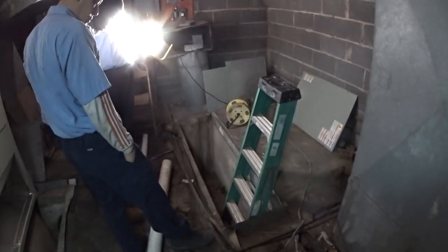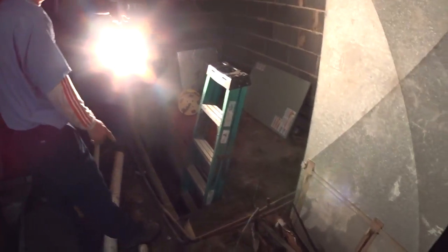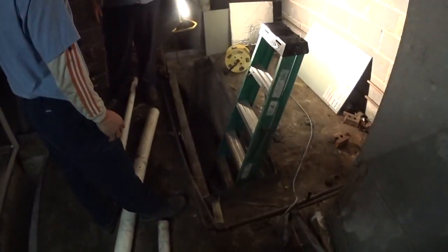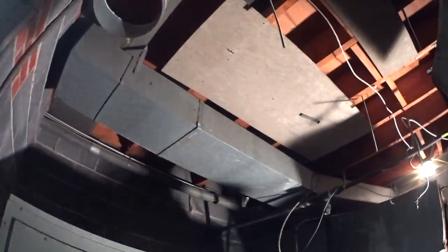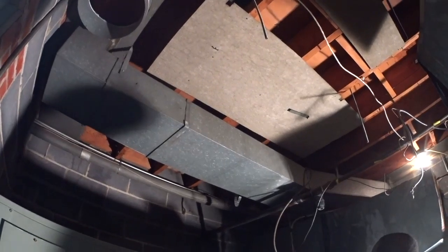You've got your two hanging heaters that's got to go up here — they used to fan out over there. We've got to move these lines before we're crushing them. Water line — we've got to cut loose, find where to shut off and cut it off and drain it. It comes through there, circles all the way around, picks up that offshoot there, comes all the way back around. We may have to take this crossover return down and pan these joists off, because those furnaces require a six-inch clearance from combustibles.